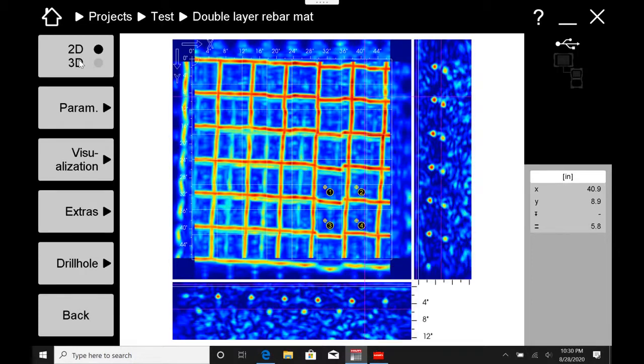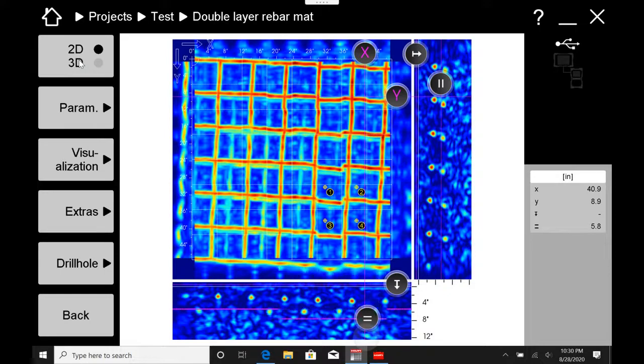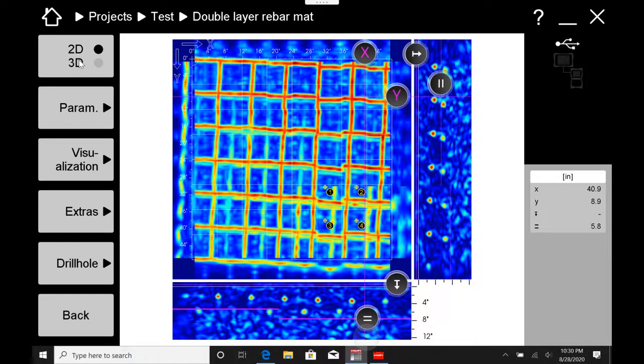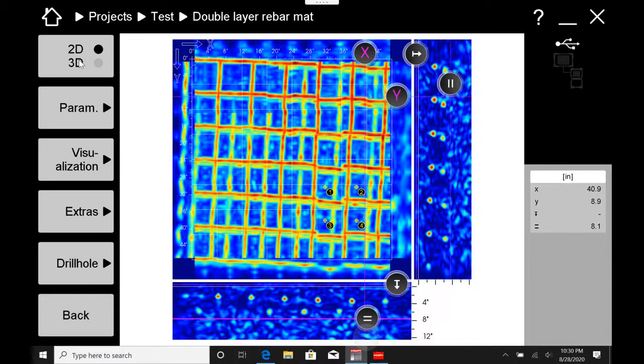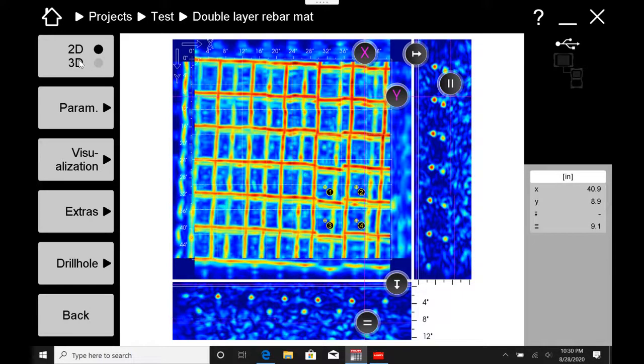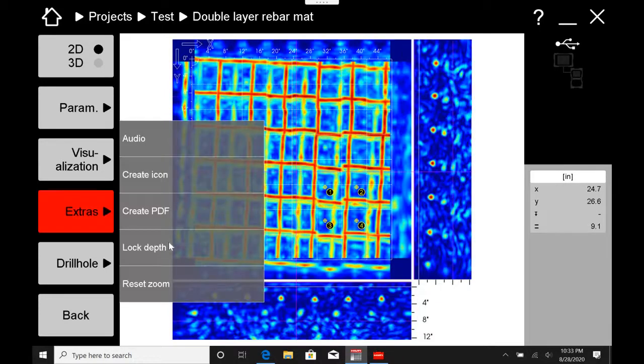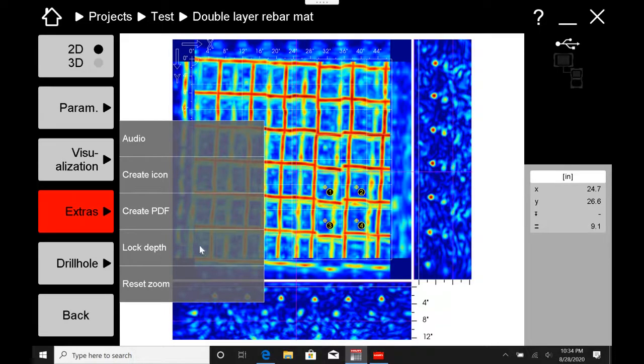So what I can do is go to extras and press this unlock depth button, and that will let me start changing it again and recalibrate my depth. It's going to warn me that the scaling will be able to be changed if I unlock it. And as long as I'm okay to do that, which I am in this case, I can go ahead and press yes in the top left corner. Once I do that, I can now come in here and if you take your finger and long press on the cross-sectional views, you'll see these icons pop up. And these are essentially the drag options for your depth. You can drag this bottom icon here that looks like an equal sign to change the thickness of the material in the concrete that you want to look at from the top or the top of your depth view. And you can see the center of the scan is changing and showing me more information. The main thing to remember is that essentially when this is locked, you don't have to worry about accidentally adjusting the settings you have to view your depth correctly that you've set. So essentially the idea is you do all you can to make sure that you've calibrated your depth correctly, you lock it in there, and then you know you're okay.